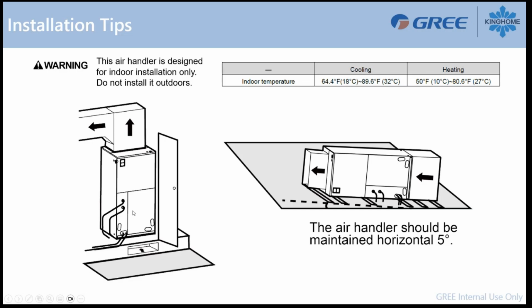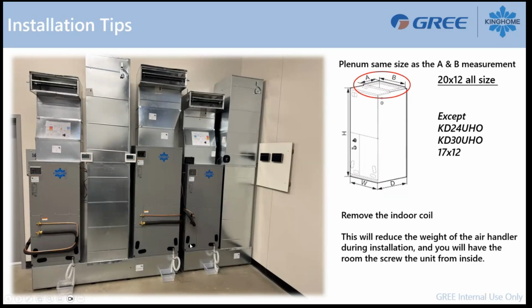Also, there's no side return for this kind of unit because we have a coil inside of it. So we need to have the air coming from the bottom of the air handler. In most installations we've done so far, we install a kind of base below the unit to build up the return air. So you can install a base just below the unit, having your return air column on one side and your air handler on the other side.